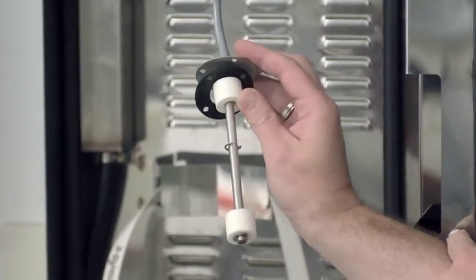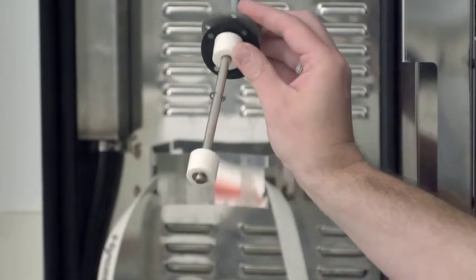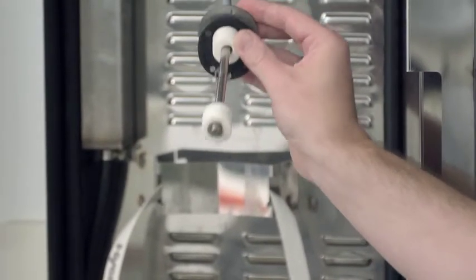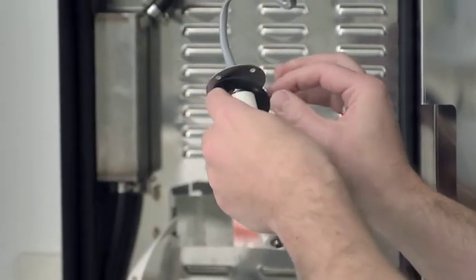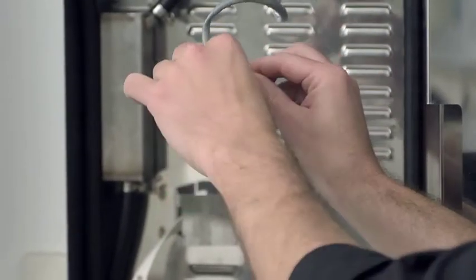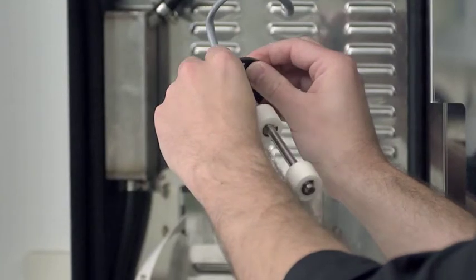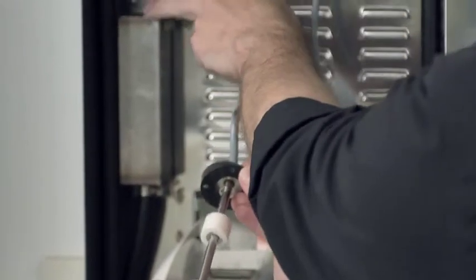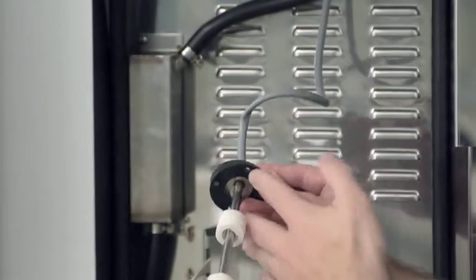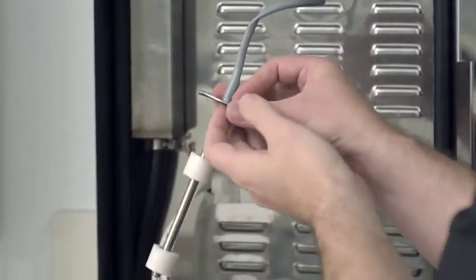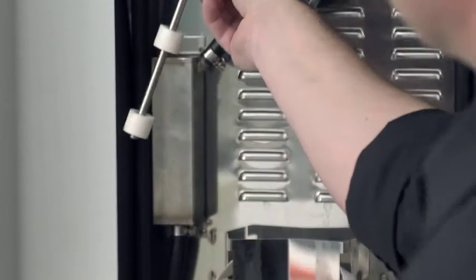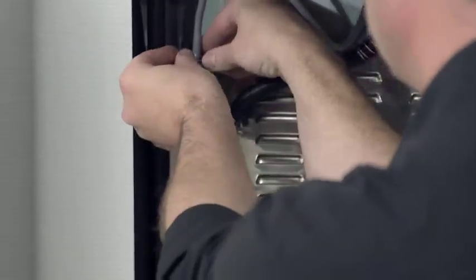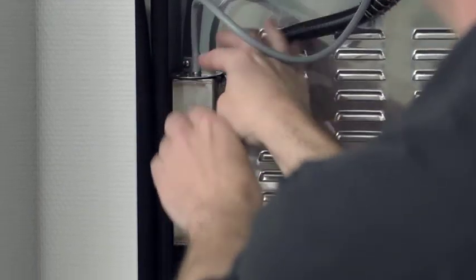After I've done that, the condition I would like to have is a metallic sheen. I can reassemble the whole thing. I can very well use the flat seal again because it will definitely seal tight. I just have to make sure that there's no coarse residue on top here, otherwise it will be hard to get it to seal right. I will reassemble this, stick that up in there, check the seating of the flat seal and then fasten the screws back on.